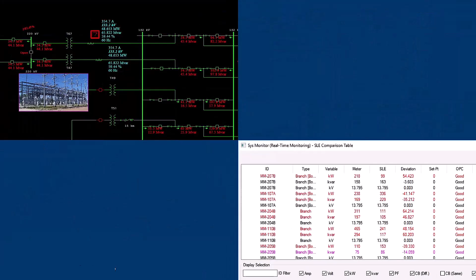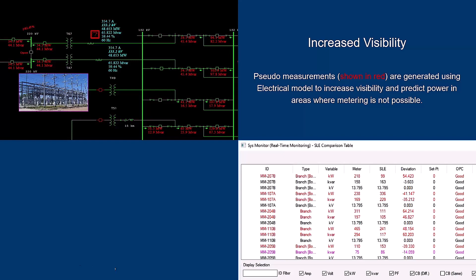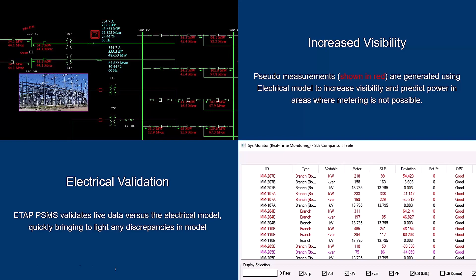ETAP PSMS will increase visibility by leveraging online data and the digital twin to create pseudo measurements, estimating the power flow across the rest of the model, including areas where metering is not possible. Additionally, ETAP PSMS will validate monitored data versus the electrical model. This is one of the advantages of using a digital twin solution. This will bring to light any discrepancies between the digital twin model and operating conditions, and will also validate the quality of all measurements from an electrical perspective.